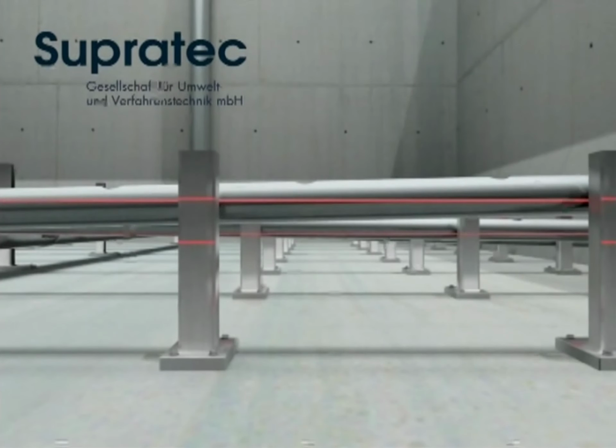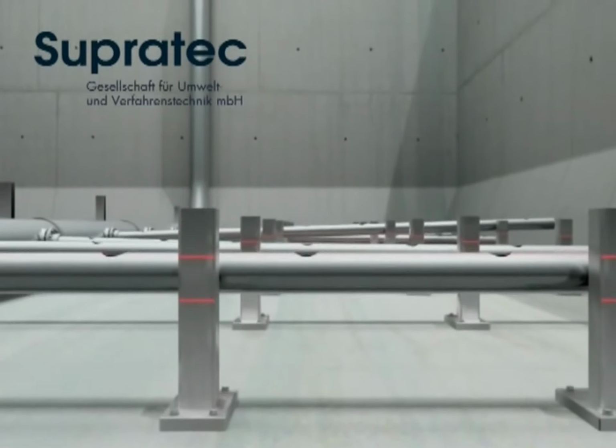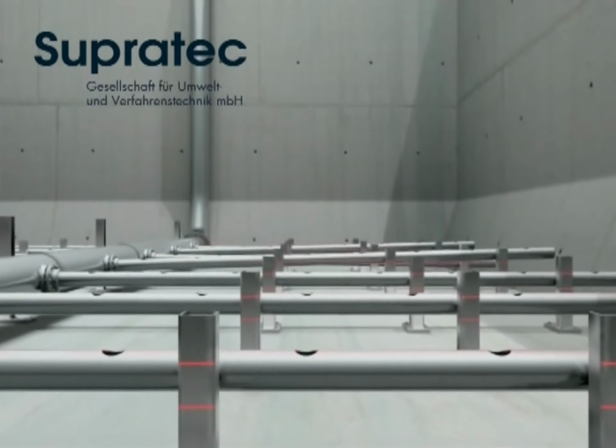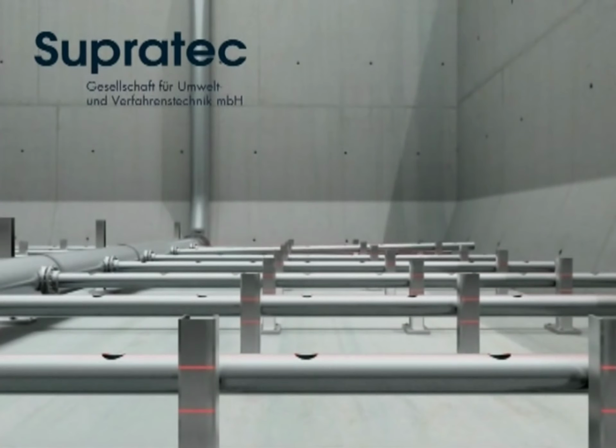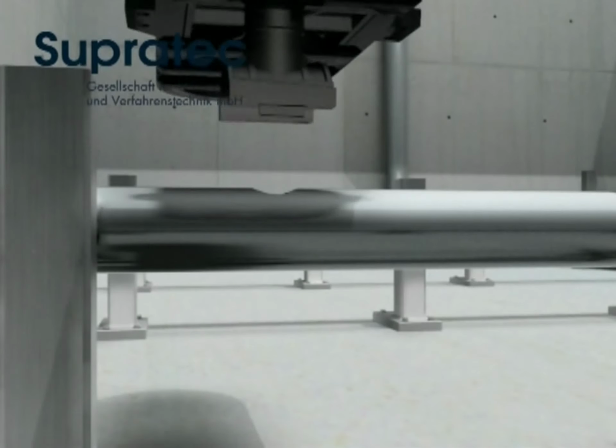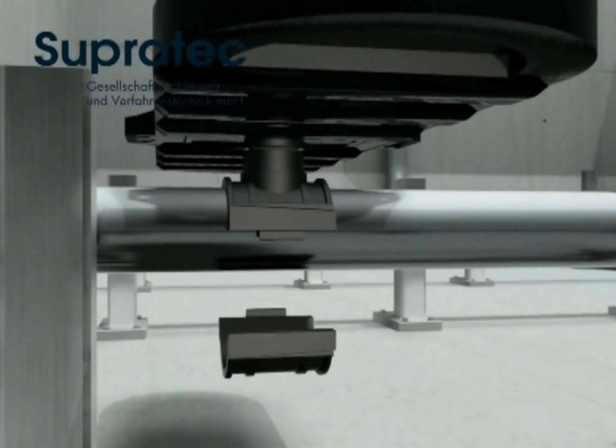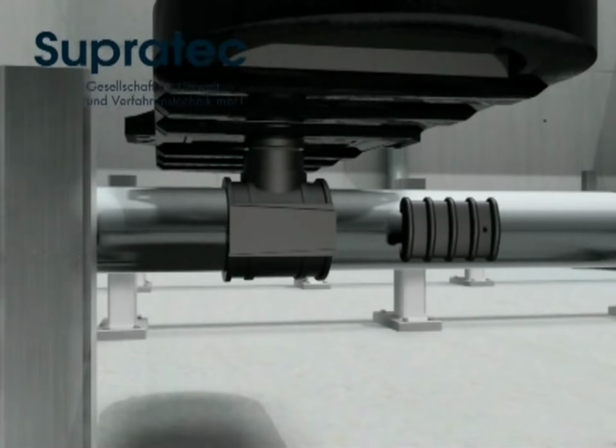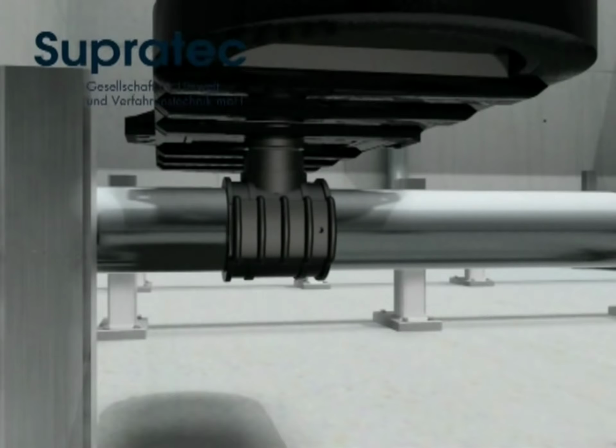All pipe supports are height adjustable to provide for leveling of the pipeline system with a laser device prior to aerator installation. The max allowable height variance is plus or minus 10 millimeters. The aerators can now be installed at the designated locations. For this, the respective aerator-specific installation instructions should be followed.